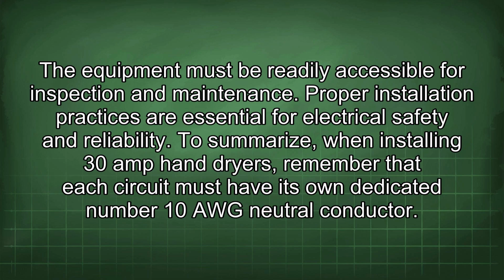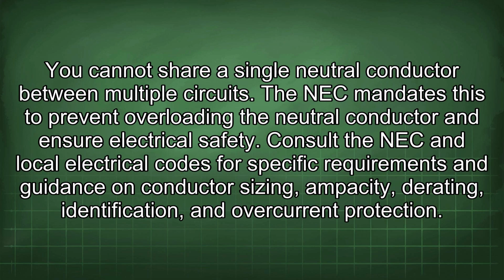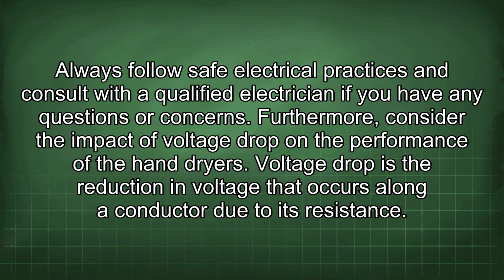To summarize, when installing 30 amp hand dryers, remember that each circuit must have its own dedicated number 10 AWG neutral conductor. You cannot share a single neutral conductor between multiple circuits. The NEC mandates this to prevent overloading the neutral conductor and ensure electrical safety. Consult the NEC and local electrical codes for specific requirements and guidance on conductor sizing, ampacity, derating, identification, and overcurrent protection. Always follow safe electrical practices and consult with a qualified electrician if you have any questions or concerns.